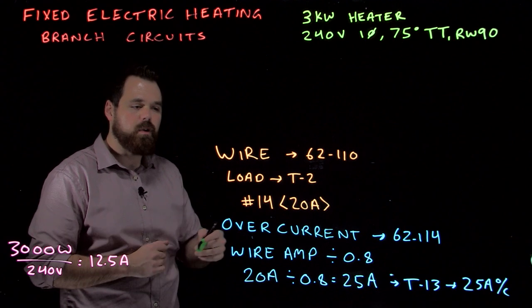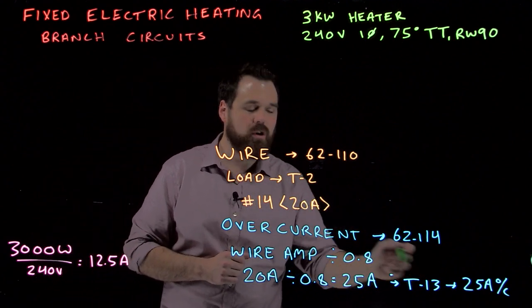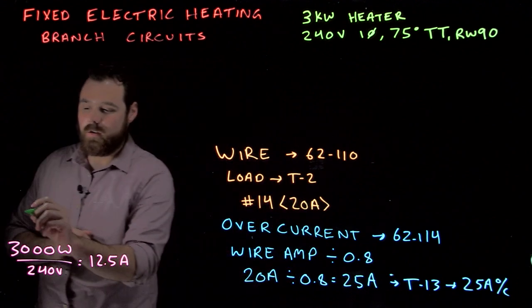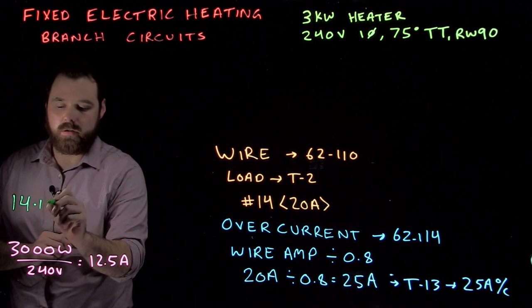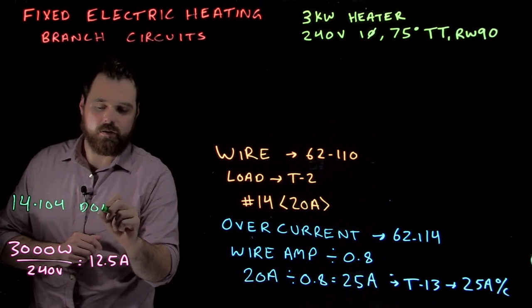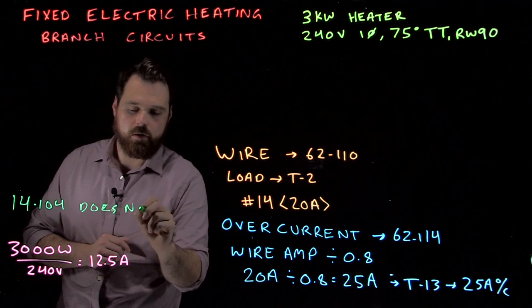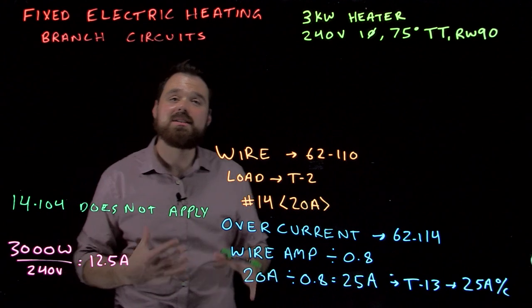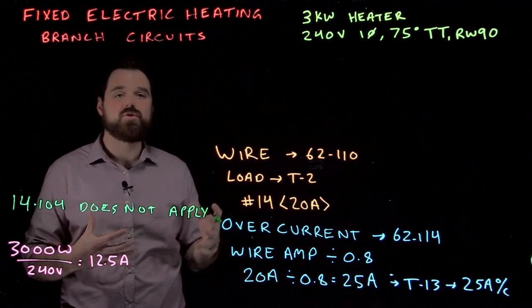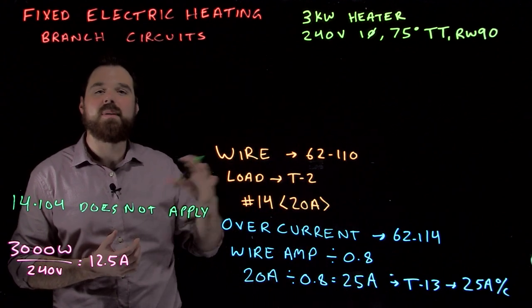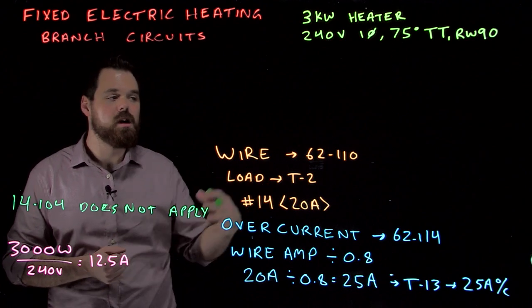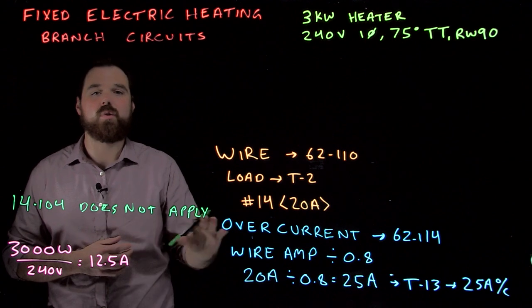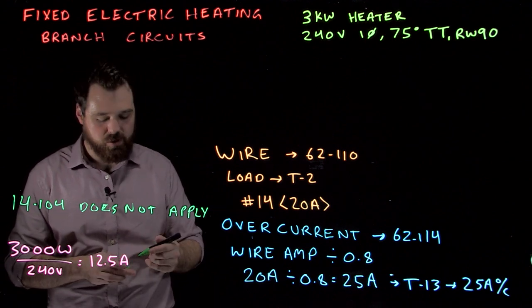Now, something has happened here. We have taken a 14 gauge and put it on a 25 amp breaker. 14104 does not apply. The reason is section 62 is a supplementary section in the code book, which means it supplements or amends the general requirements of the code. So because section 62 says we can do this, we can do it and we don't need to worry about the breaker size on that number 14.